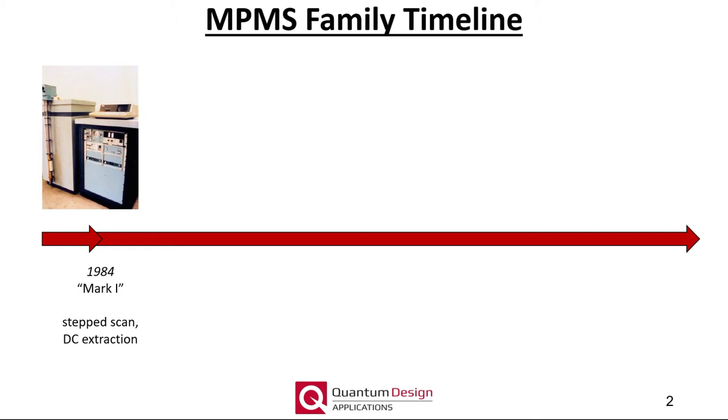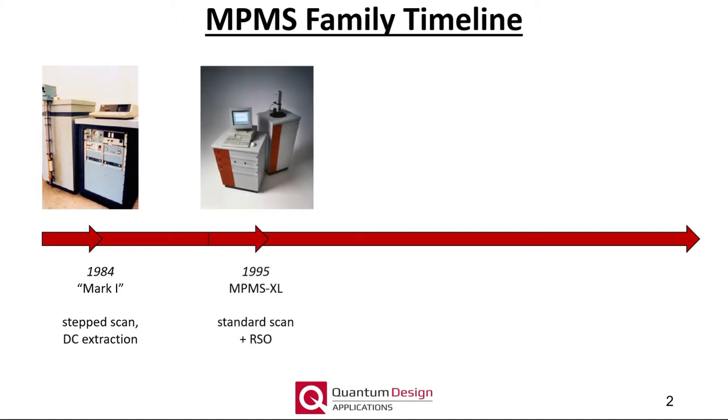A little bit of history. The magnetic property measurement system, or MPMS, was born in 1984 as the so-called Mark 1 or classic MPMS. The Mark 1 utilized a stepped DC extraction method to measure the magnetic moment as a function of temperature and/or magnetic field. In 1995 the MPMS XL was launched and included the reciprocating sample option or RSO, which further improved measurement sensitivity. In January 2016, Quantum Design announced the obsolescence of the MPMS Classic and XL, and that part availability cannot be guaranteed after 2020. Many of the OEM electronic components needed in board manufacture were obsoleted many years ago and are extremely difficult to find. Despite these challenges, we would like to continue to keep the legacy MPMS instruments operational as long as parts are available.